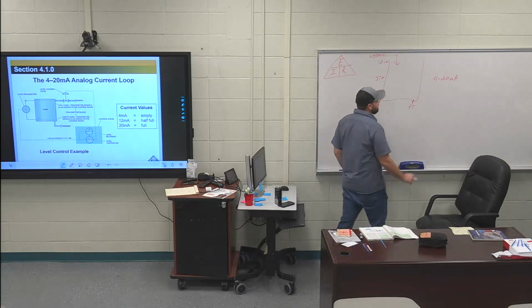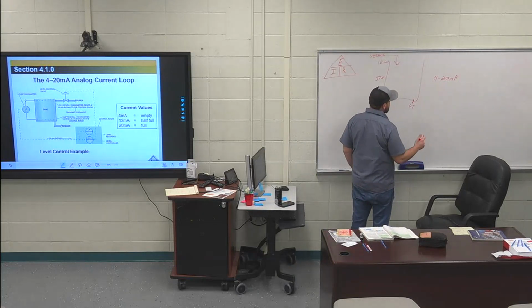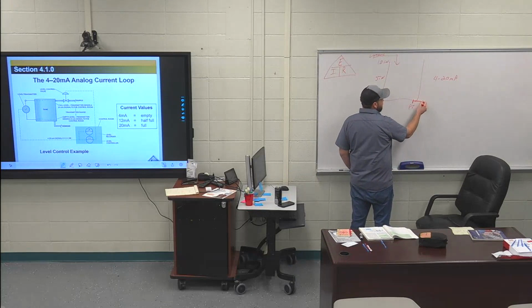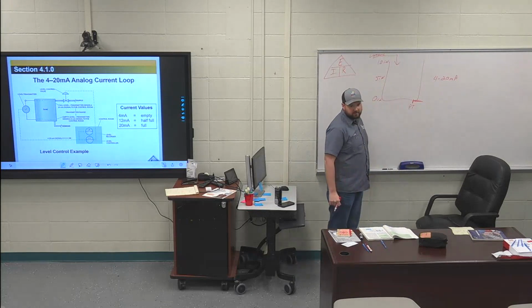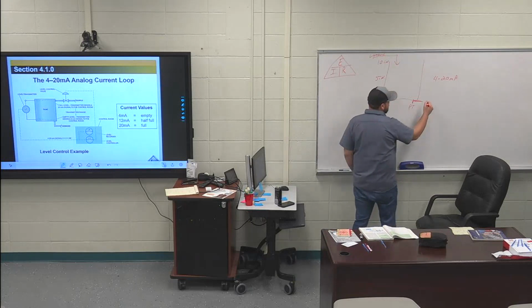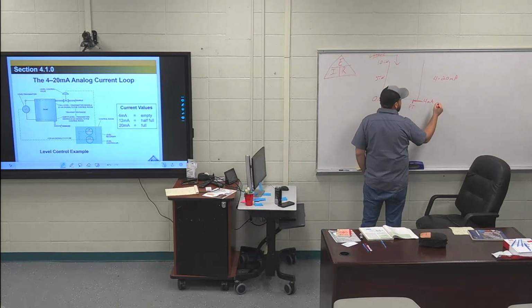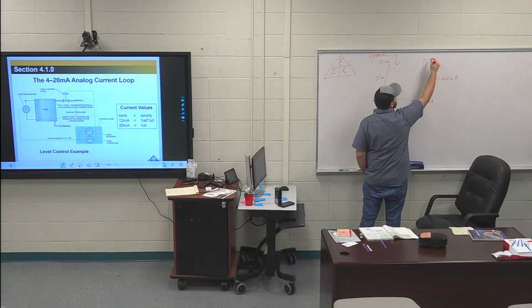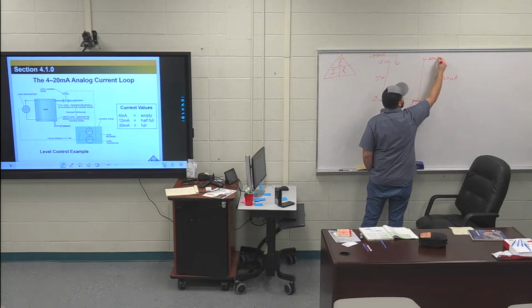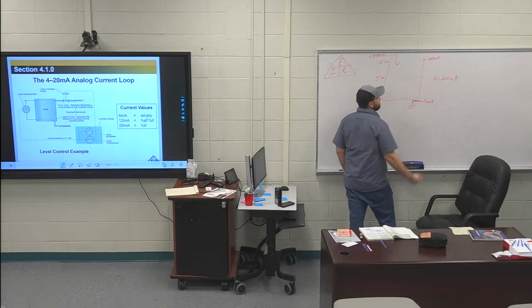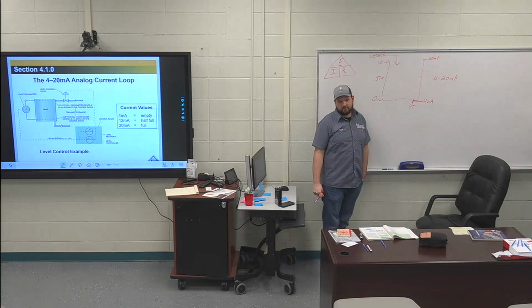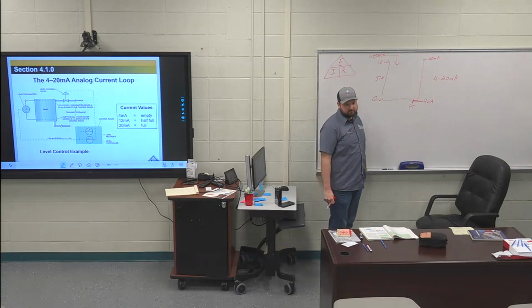So if 4 to 20 is my range, what is my milliamp reading going to be at 0 inches? 4 milliamps. What's it going to be at 10 inches? 20. All right, trickier one: what's it going to be at 5 inches? 12.